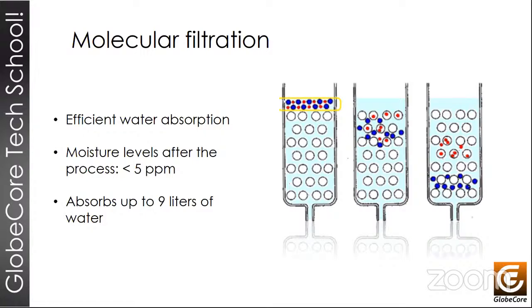Because if we eliminate those gases, we'll have no way of telling the condition of the oil or deterioration of the transformer. There are filters that can hold up to, say, 9 liters of water that they extract from the oil. And the end result, the dryness can be as low as 5 ppm of water in the oil. It's considered quite a low amount of moisture for a transformer. Next, please.